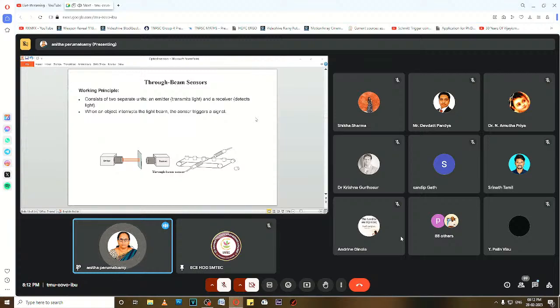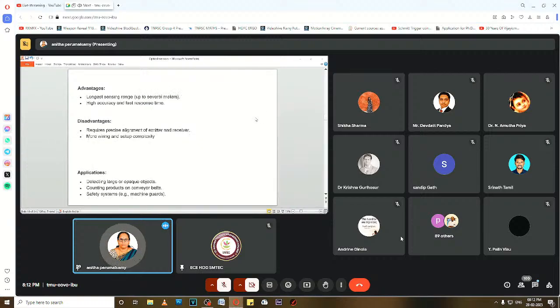The separation of the emitter and receiver allows through beam sensors to achieve superior detection accuracy. That's why it has a high accuracy and range compared to the other two photoelectric sensor types. So this is the working principle. Due to this nature, it has a significant advantage: it can sense the longest sensing range. One of the best parts of a through beam sensor is its ability to detect objects over long distances, often extending to several meters. That's the beauty of this sensor.